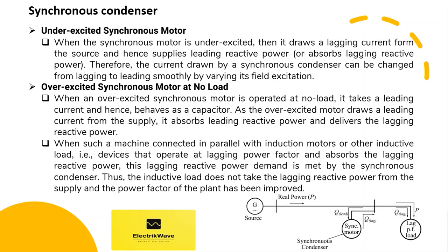When the synchronous motor is underexcited, it draws a lagging current from the source and hence supplies leading reactive power or absorbs lagging reactive power. Therefore, the current drawn by a synchronous condenser can be changed from lagging to leading smoothly by varying its field excitation.